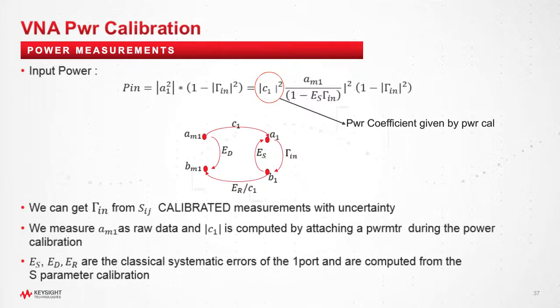If you make the calibration now and you make the measurements tomorrow, then you will have drift to account for. But I would highly discourage that. If you want to make accurate measurements, make the calibration now and make the measurements right after. Don't wait one week or one day, or turn the instrument on and off, because that will increase your uncertainty just by the drift of the instrument itself. Sure. Right. Okay.